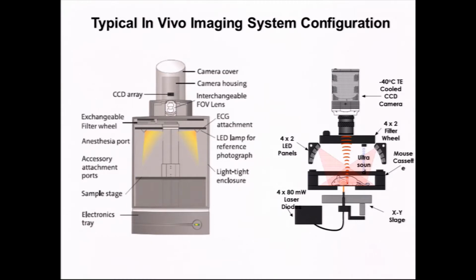Or you can also have fluorescent imaging platforms. The major difference between these is with a fluorescence dedicated imaging platform, you don't need such a cooled system. It can be cooled to minus 40 as opposed to minus 90 or below. This allows you to get more sensitivity. It also allows you to detect further into the red as well. So these are the two real configurations that people have when they're developing optical imaging platforms that offer small animal imaging.